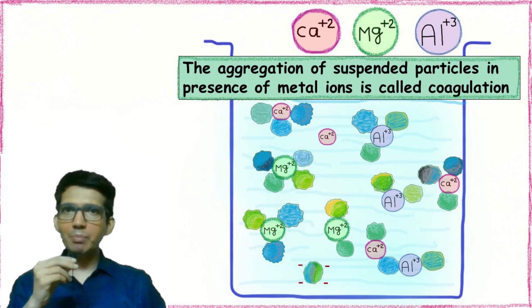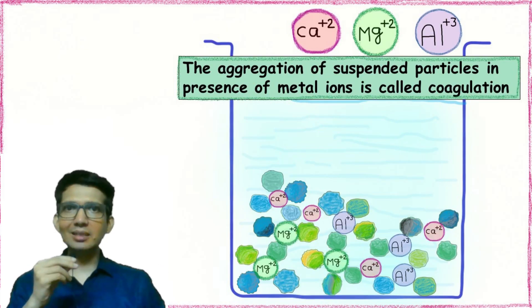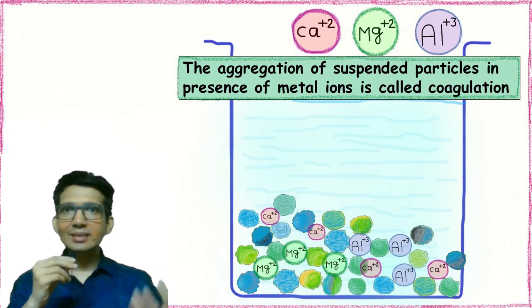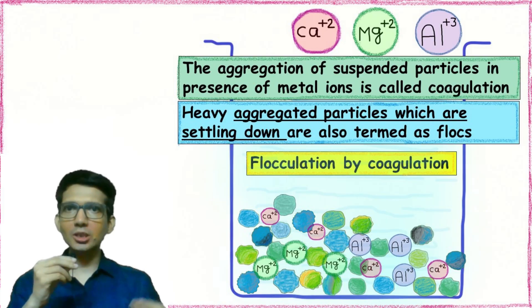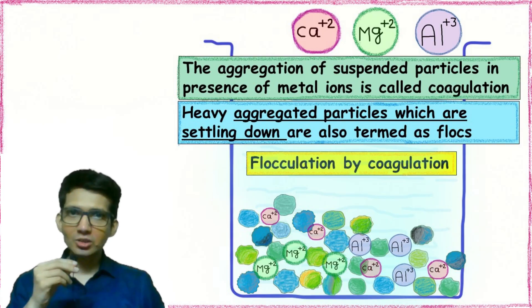Once the aggregate becomes heavy, it settles down. These heavy aggregated particles which are settling down are termed as flocs. And the mechanism is termed as flocculation by coagulation. This means we have formed these flocs by the addition of coagulants like metal ions.